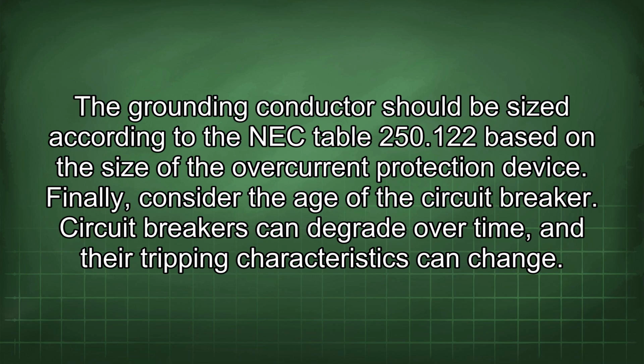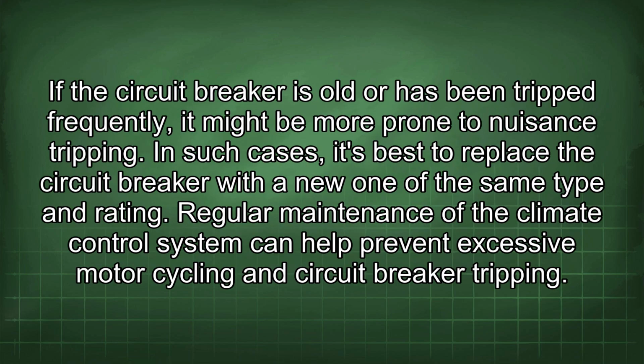Finally, consider the age of the circuit breaker. Circuit breakers can degrade over time, and their tripping characteristics can change. If the circuit breaker is old or has been tripped frequently, it might be more prone to nuisance tripping. In such cases, it's best to replace the circuit breaker with a new one of the same type and rating.